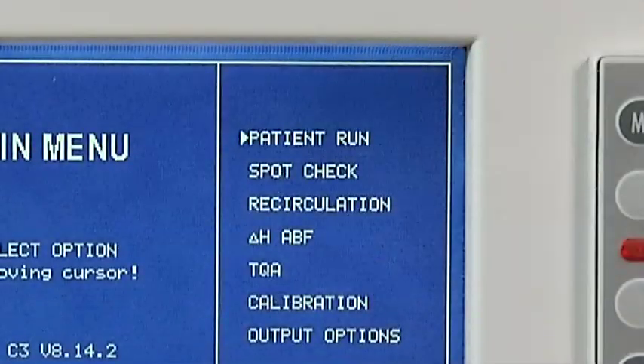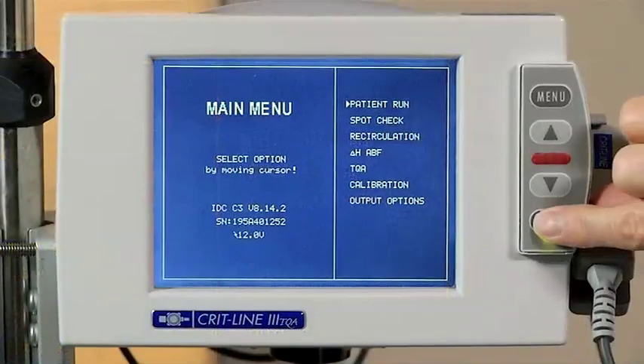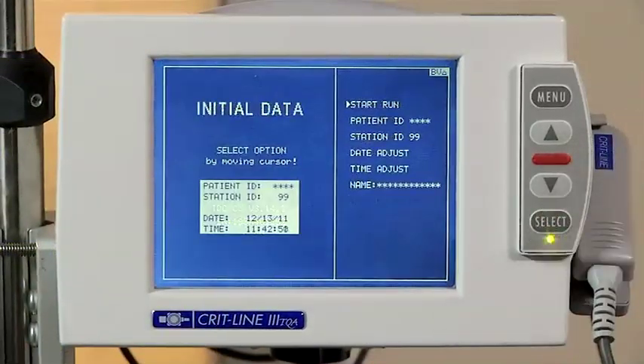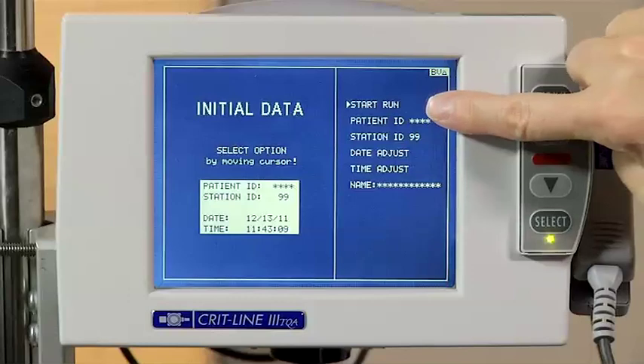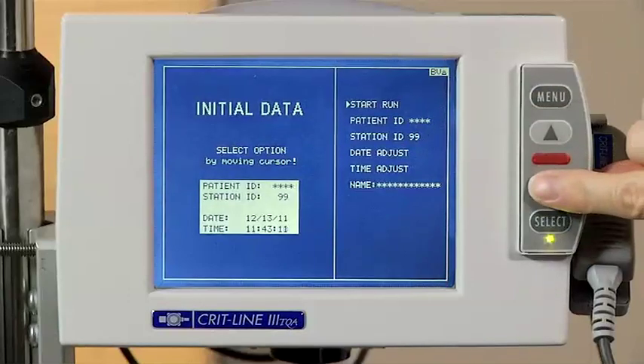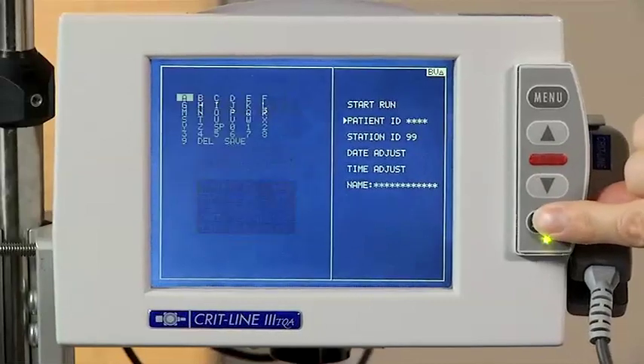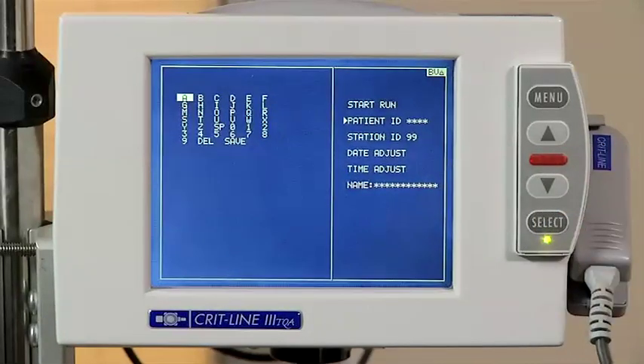From the main menu, move the cursor to Patient Run, and then press the Select button to advance to the Initial Data screen. The Initial Data screen allows you to enter specific patient identification information prior to beginning a treatment. You can also verify the date and time in this screen. Make any corrections as necessary. To enter a patient ID, scroll to Patient ID and press the Select button. You can then enter up to a 4-digit alphanumeric ID number.